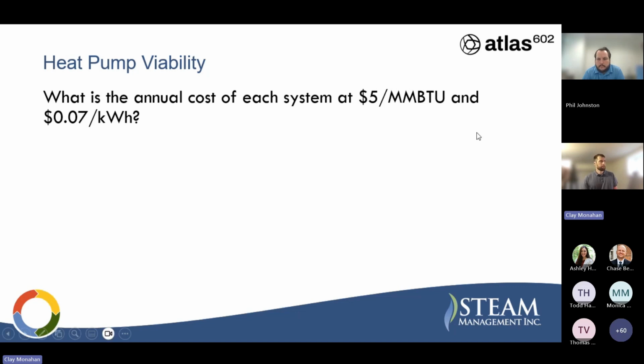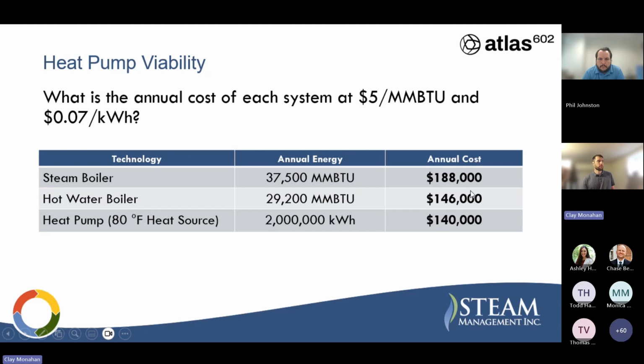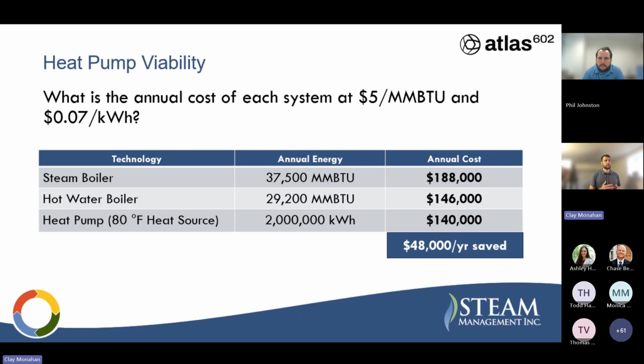We'll get into that in a second. So a steam boiler under these parameters is going to cost 188,000 with that same energy value we just calculated. Hot water 146, and then a heat pump is at 140. So in these conditions, we're only seeing about $48,000 a year saved. And I think it's worth noting, these systems at $3 an MMBTU to get the heat pump purchased and integrated.